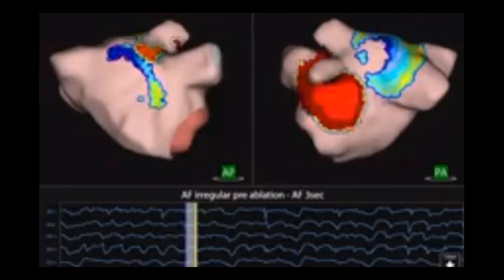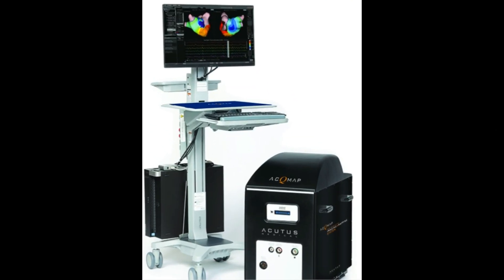This should be particularly useful during cardiac ablation procedures when monitoring the heart's response to treatment. The ACQMAP system is able to provide global dipole density mapping of irregular and short activation in the atrial chambers, whereas conventional sequential mapping may struggle to provide the information required. The system has been tested for real-time mapping of complex arrhythmias.